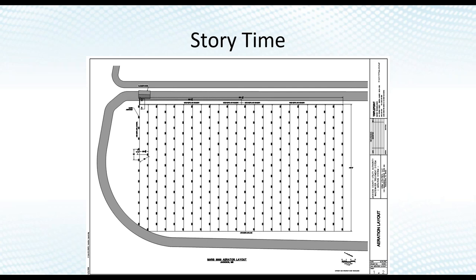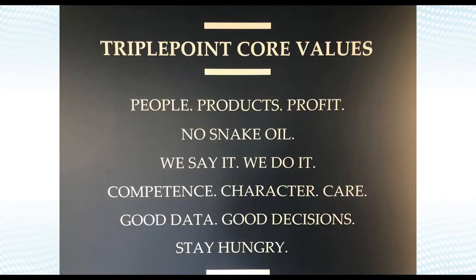Surface aerators are well-known to not be the most efficient type of aeration. They knew they wanted fine bubble but wanted to maintain mixing, which is why they went with Triple Point. We designed a system of 288 units based on 1.9% per foot efficiency. I consider morality pretty important to me and to our company. We're a principled organization — we always put our relationships and products above profit. We don't want to sell snake oil.